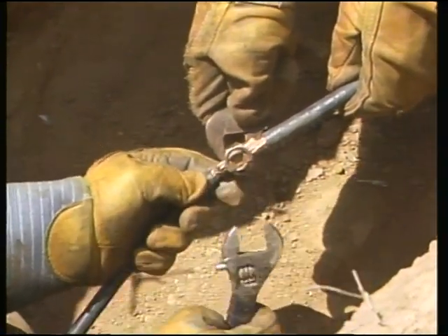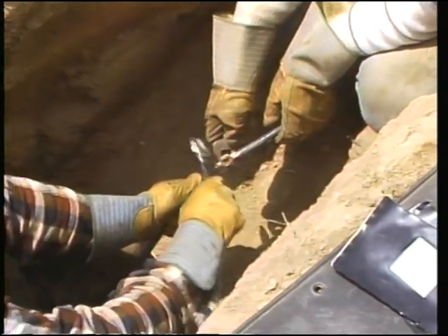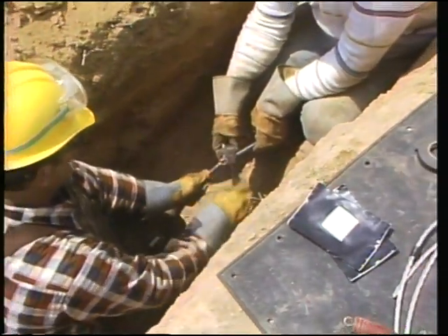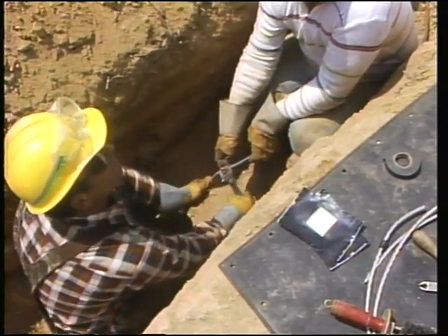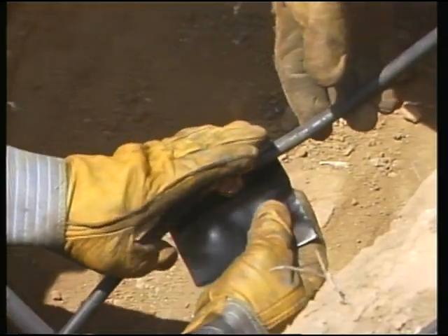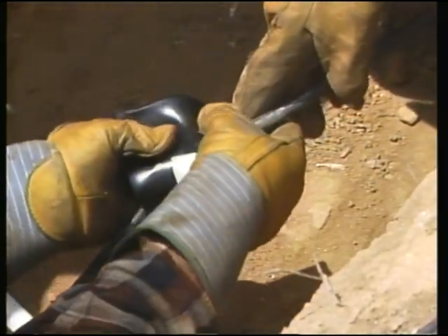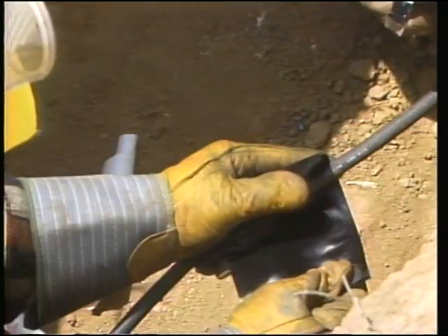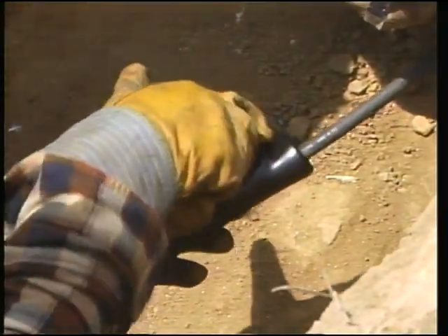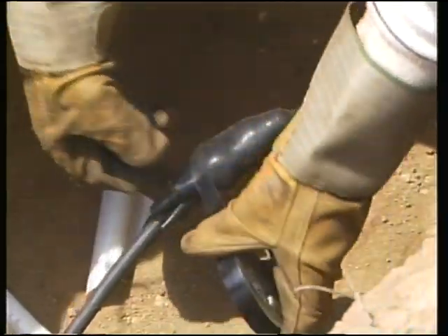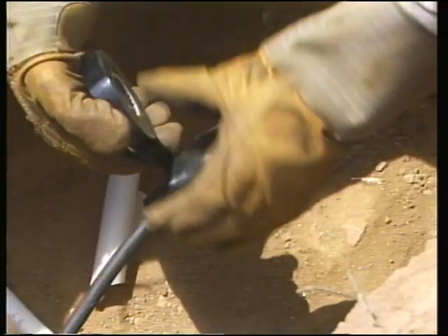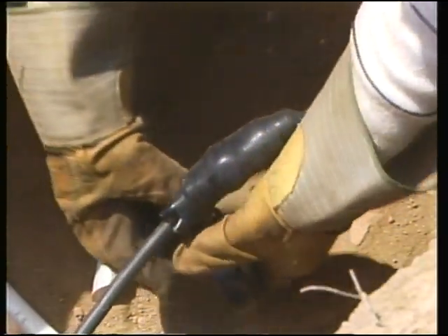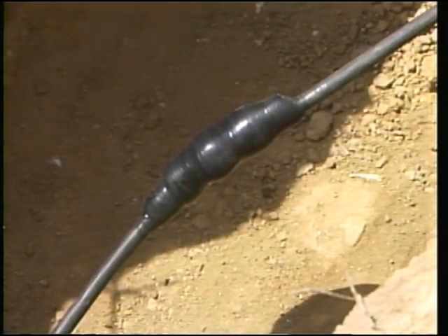To make sure the connector is on tightly, the workman taps the cable or connector and then retightens the split bolt. Around the splice, the workman places 2 pads made of an insulating putty material. The pads are wrapped around the connector and the exposed conductor and then adhered to each other. The pad is wrapped with a layer of plastic tape to make a better seal around the splice, and the splice is complete. This split bolt splice is usually just used as a temporary fix.